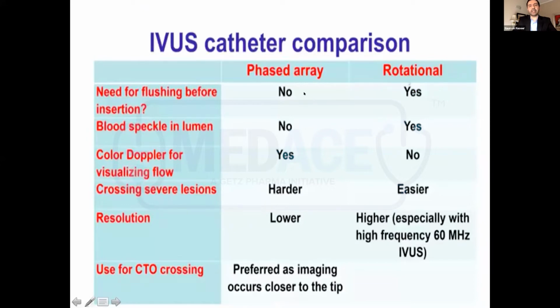That is the rotating catheter, and phased array is a fixed transducer catheter. It does not need any flushing before insertion, while the rotational catheter needs flushing before insertion. You can have some blood speckle in the lumen with the rotational catheter, which is not seen with phased array catheters. And there is the option of ChromaFlo, which is color Doppler for visualizing lumen flow, with the Volcano catheter, which is not available with rotational catheters.